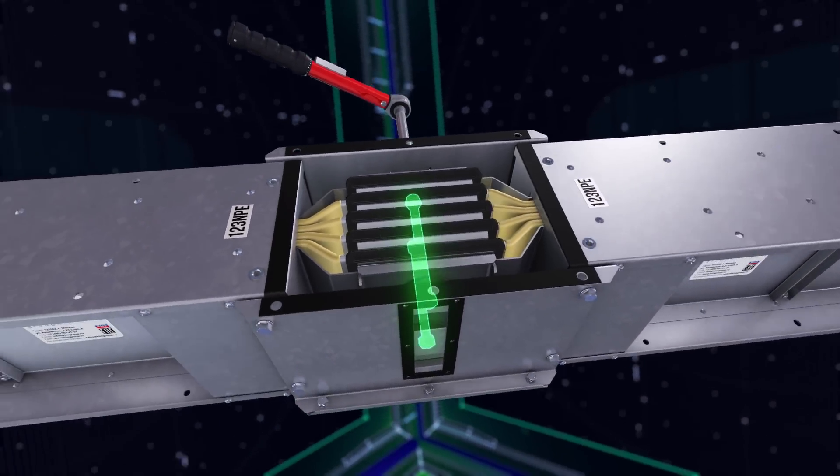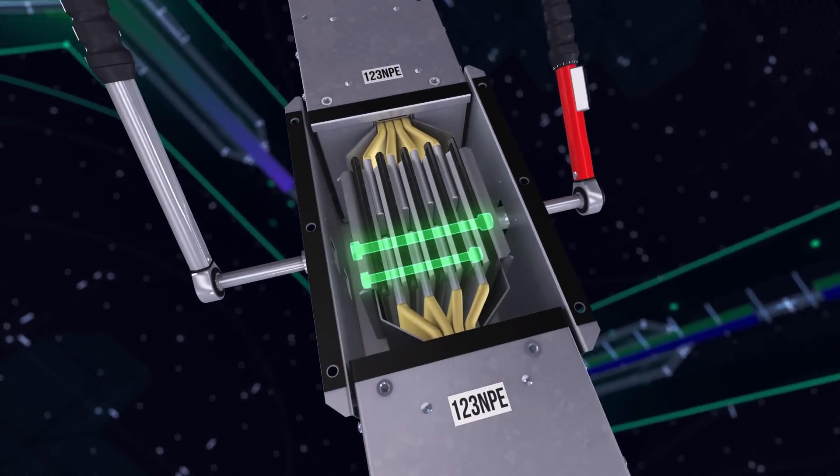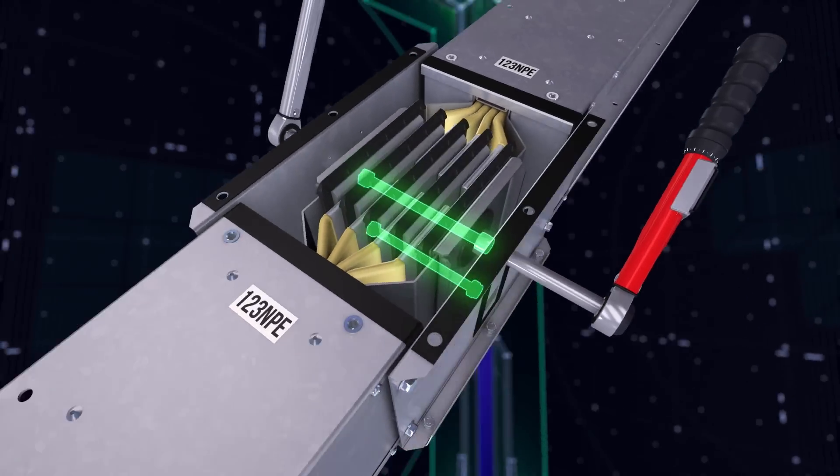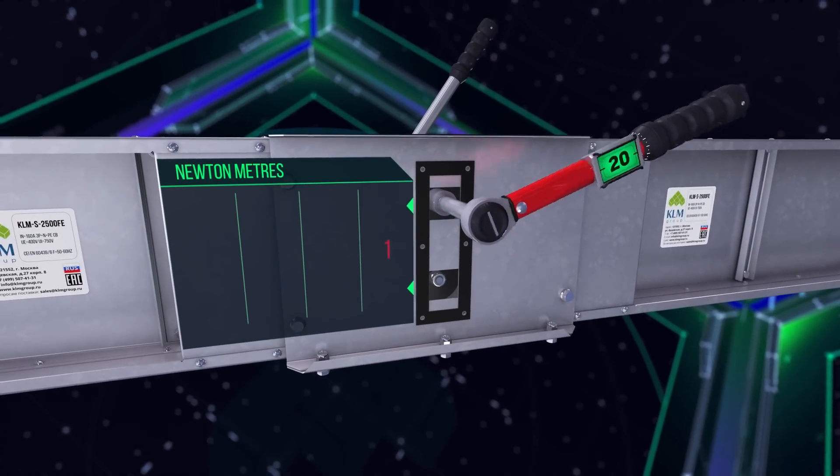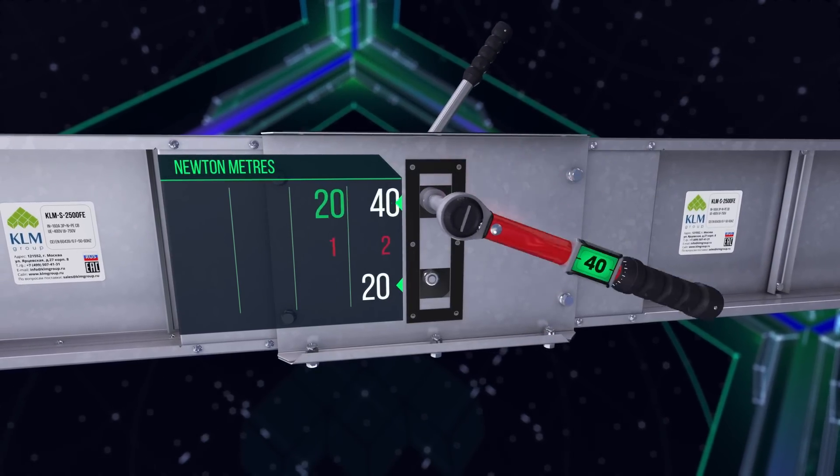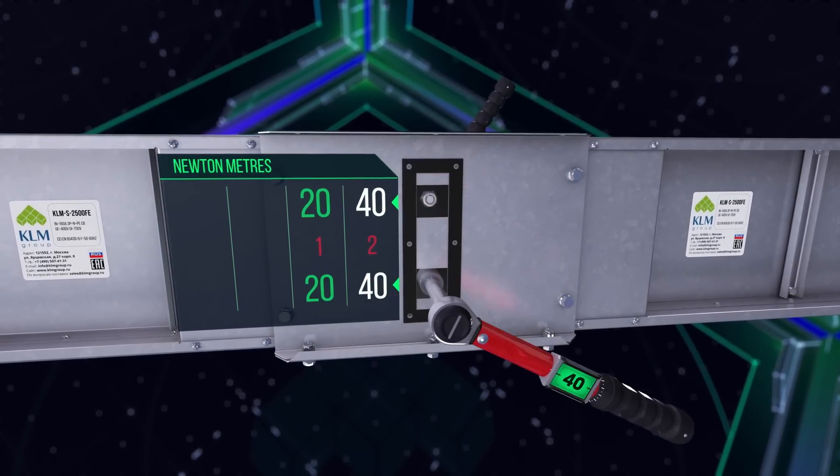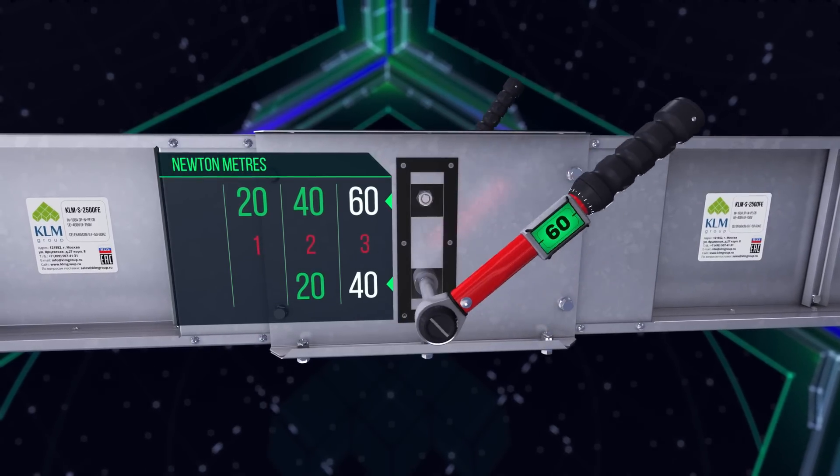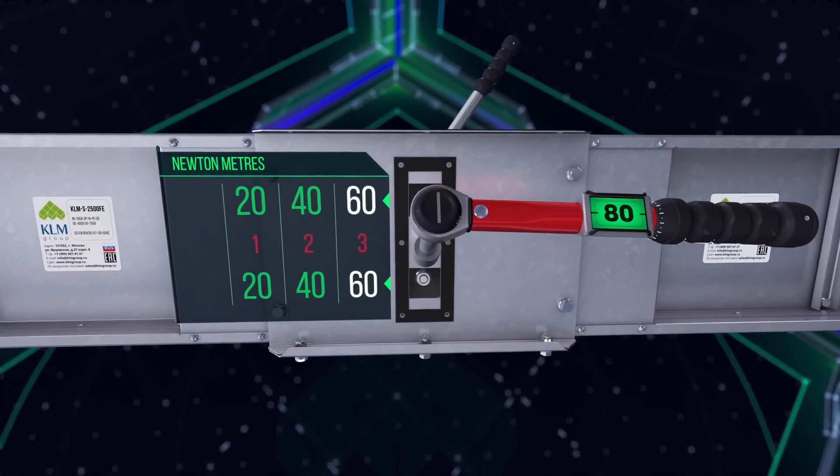Tighten the junction unit clamping bolts in rotating sequence while holding the bolts fast from the other side. This procedure should be performed with a torque spanner in four stages using the following torque settings: In the first stage, the torque spanner should be set to 20 newton meters. In the second, to 40. In the third, to 60. And in the fourth, it should be set to 80 newton meters.